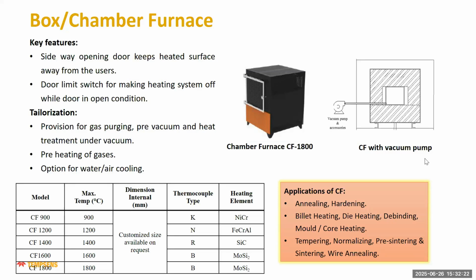For CF 1600, we have a maximum temperature of 1600. The thermocouple type can be B, and the heating element can be molybdenum disilicide. Then we have model CF 1800, which can go up to 1800 degrees centigrade. Thermocouple type can be B, and the heating element will be molybdenum disilicide. Applications of the CF furnace can be annealing, hardening of big material, billet heating, die heating, debinding, mold and core heating, tempering, normalizing, pre-sintering, sintering, and wire annealing.